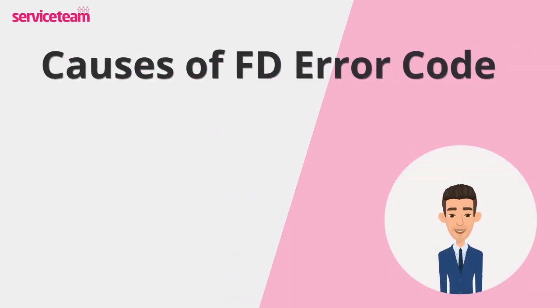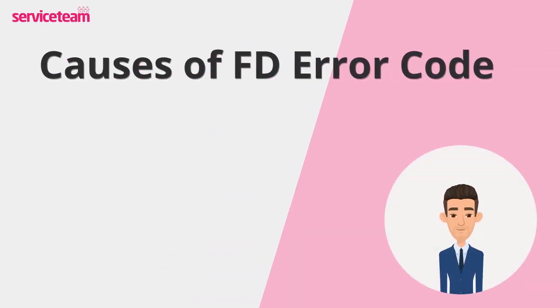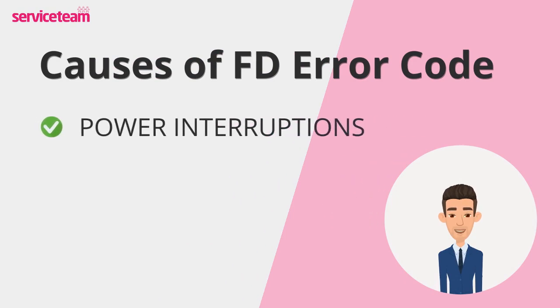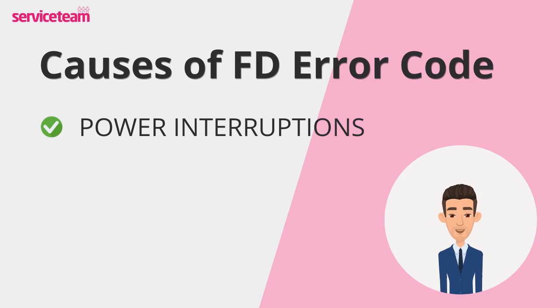Let's see what causes the FD Worcester error code. Starting with the most common cause — a power loss to your boiler. This could happen due to a power outage in your home, a tripped circuit breaker, or an issue with your electrical supply.